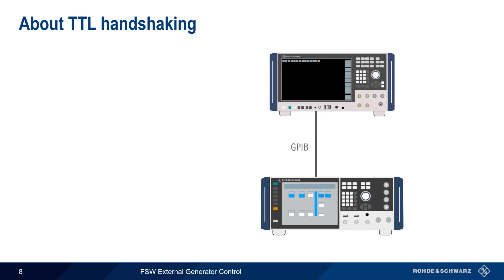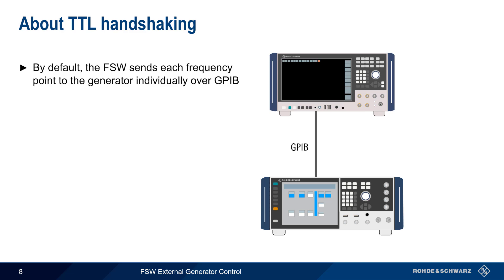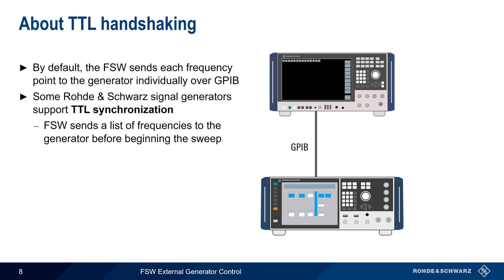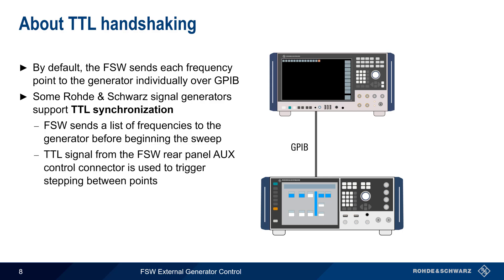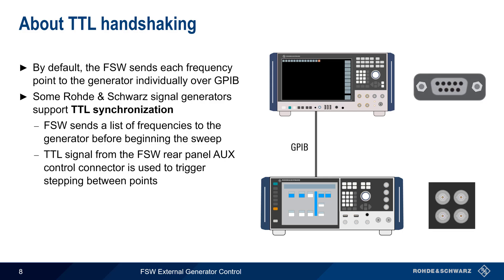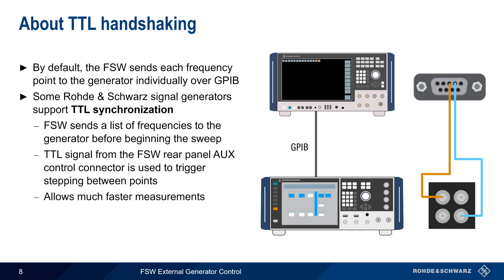Now let's come back to TTL handshaking. When the FSW and generator are connected over GPIB, the default behavior is that the FSW sends each frequency point to the generator individually. Some Rohde & Schwarz signal generators support TTL synchronization. When this is enabled, the FSW sends the entire frequency list to the generator before beginning the sweep. A TTL signal from the FSW's AUX control connector then triggers the generator to step to the next frequency point in the list. TTL handshaking therefore allows much faster measurements when using GPIB as the connection method.